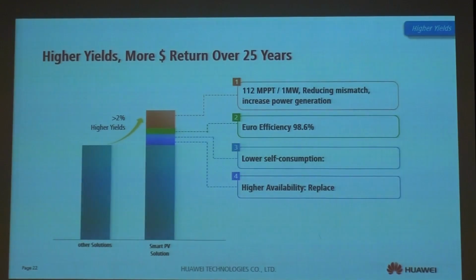The first part is the multi-MPPT design. As mentioned, our inverters use multiple MPPTs—for example, a 36 kilowatt inverter has 4 MPPTs, while new 50 or 60 kilowatt products have 6 MPPTs per inverter. So for a 1 megawatt PV project, there are more than 100 MPPTs in total. More MPPTs help reduce mismatch, and less mismatch means more generation.